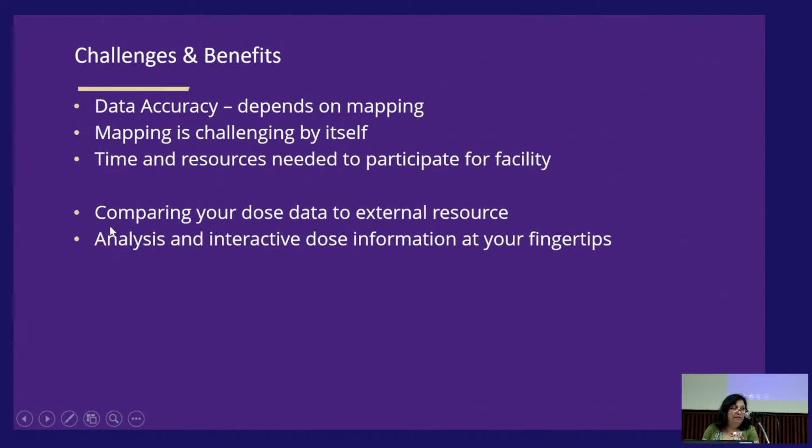But what are the benefits? Comparing your dose data to an external resource, I think that's extremely important. You might think you're optimized, but when you compare, you might be 20 milligray higher than the rest of the country, which says something about your facility. So I think that's the biggest benefit. Analysis and interactive dose information at your fingertips. You can play with the data the way you want.